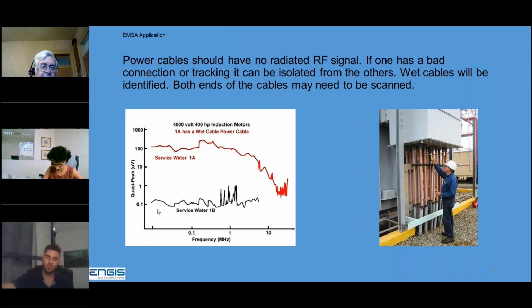The 1B motor, there's almost no noise at all. We stopped at 30 megahertz, below 10 megahertz on this one. Local radio station, this is the noise floor of the equipment. So the 1B motor and cables are fine, but 1A is much higher. One, two, three orders of magnitude more noise. It was corona. And they opened up that tunnel that this cable was in, and it was full of water. So that was the signature of a wet cable. So comparing two at the same location, obviously 1A you need to work on.